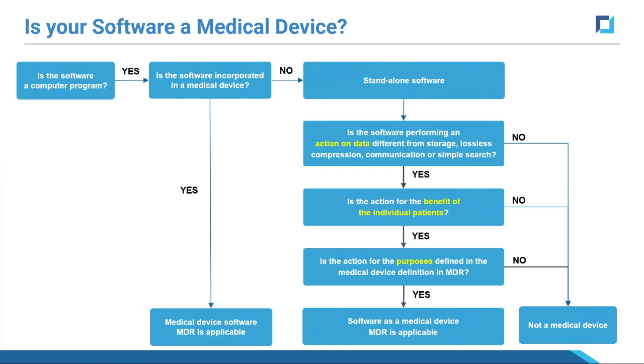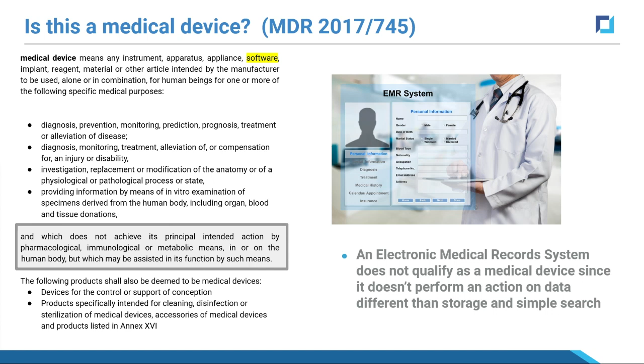So this was indeed the question that we had before, and the answer is no, it does not qualify as a medical device since there is no action on the data, different than storage and simple search. And then another important note to wrap up here: the intended use is important, and the claims that are made by the manufacturer, it's really the claims that are made by the manufacturer that are important.